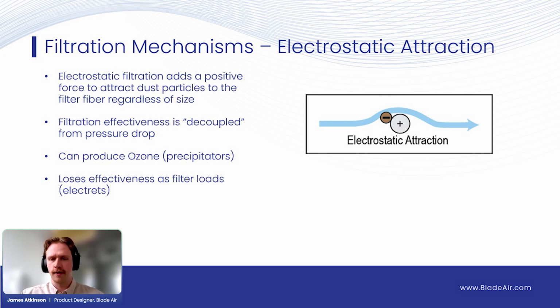Then there's another filter called electret, which is an electrostatic filtration. It has a charge already applied when it leaves the factory, but as it traps dust, that charge is absorbed by the dust being collected, so it loses effectiveness as it loads with dust. There are some advantages though — I'll talk more about our Pro filter later and how it tackles those problems.